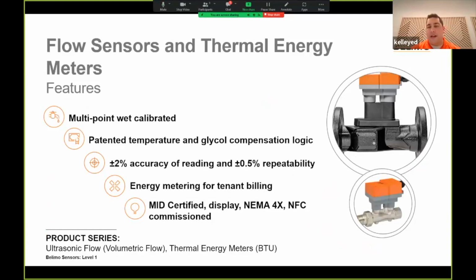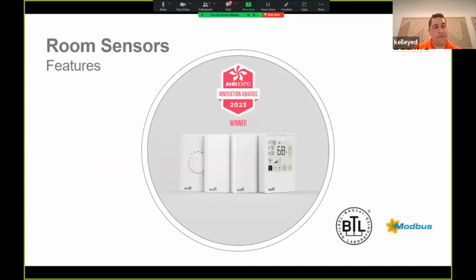Jumping to flow sensors here, guys. If you're familiar with EPIV, energy valve, and so on, those are a performance device from Belimo that include our flow sensor as a component. The big claim to fame with Belimo flow sensors is glycol compensation. In real time, it measures the glycol in the system, and it spits out a true accurate flow reading. Belimo owns this patent. We won all sorts of awards on this. Again, if you want any additional information, feel free to reach out, ask questions and so on, and we can chat on this stuff towards the end of this call.